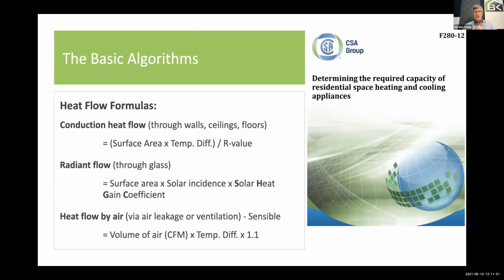And so I always like to report on the fact on the right-hand side that we have a relatively new, that is 2012, it's actually been updated already in 2014 and again in 2016, we have this lovely CSA standard called F280 that's used to determine the required capacity for space heating and space cooling, as CSA F280. You'll hear me refer to it a number of times. And within that standard, I want to remind you, everything in there is conservative.